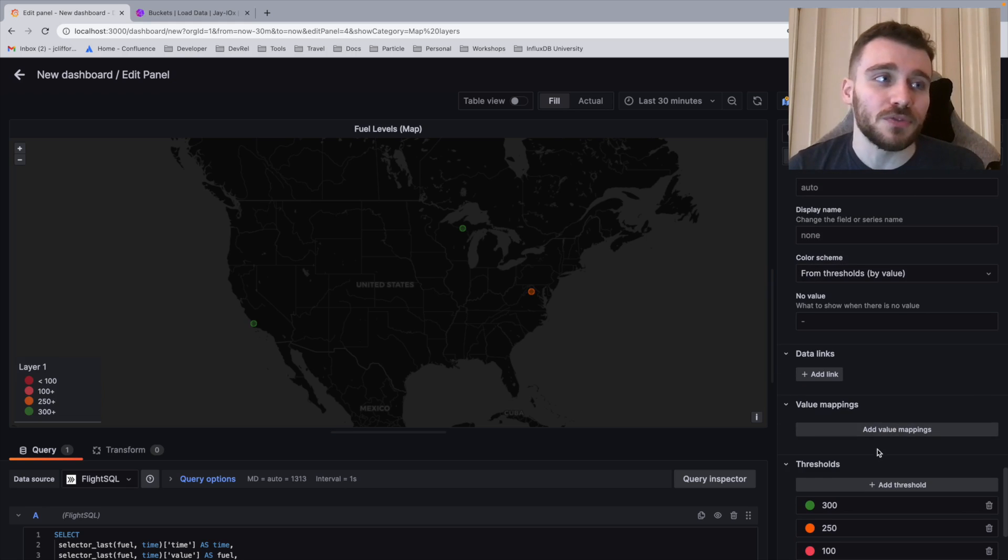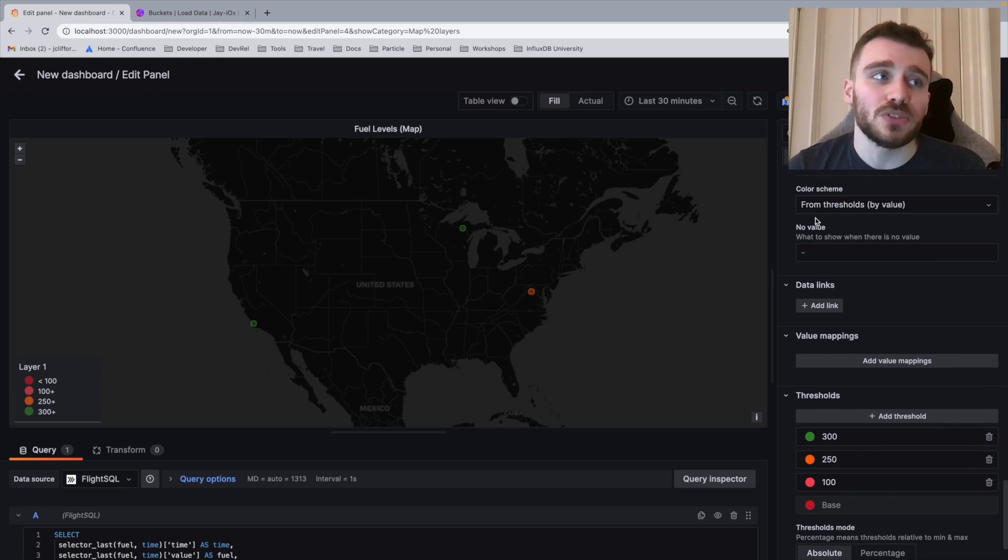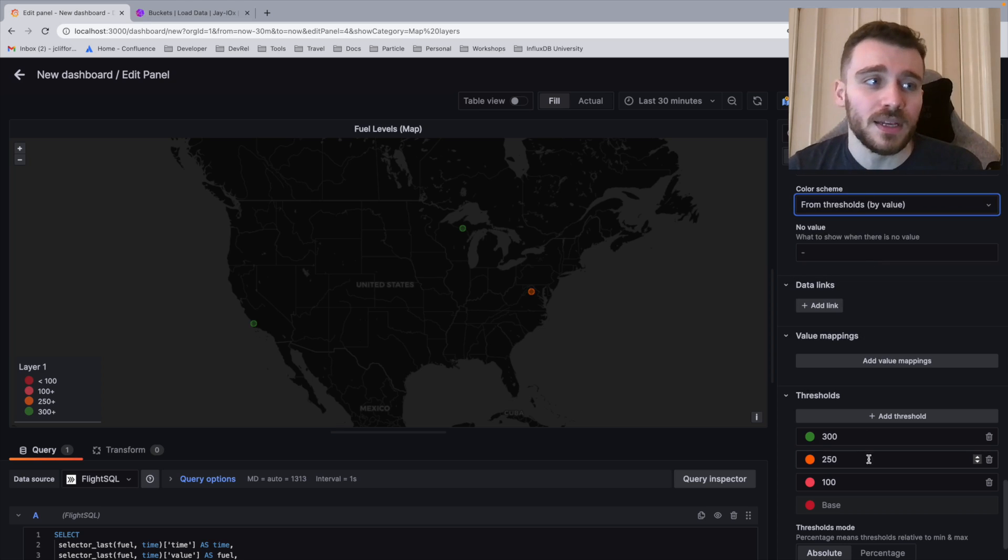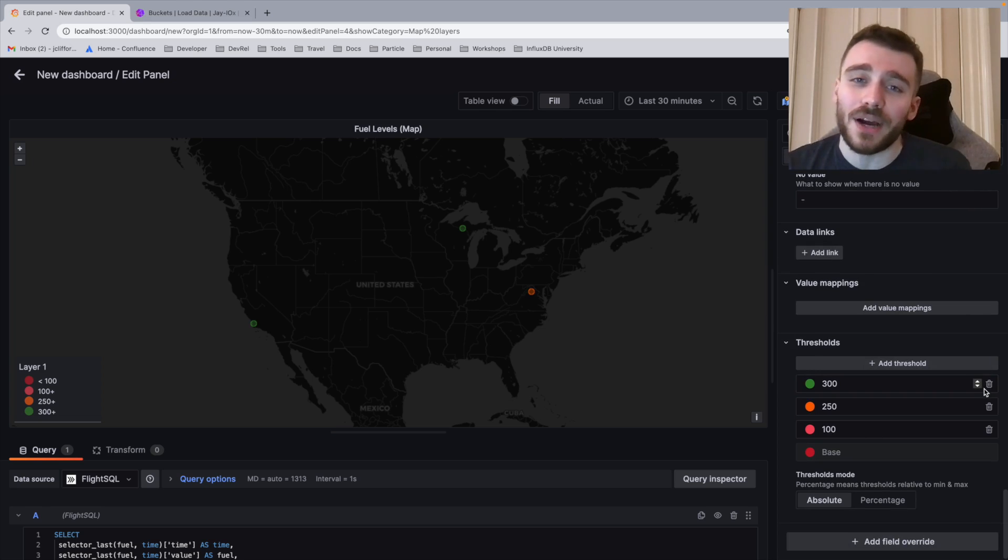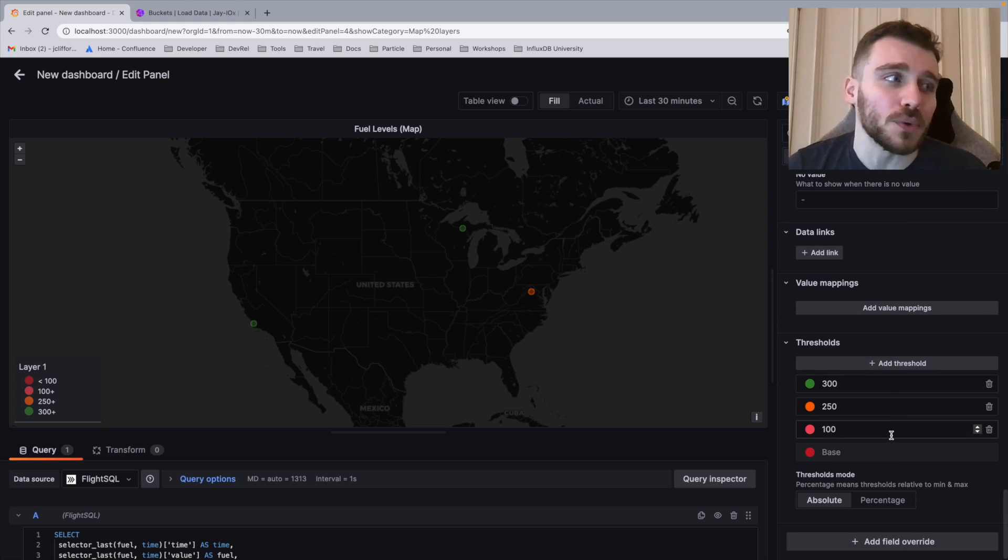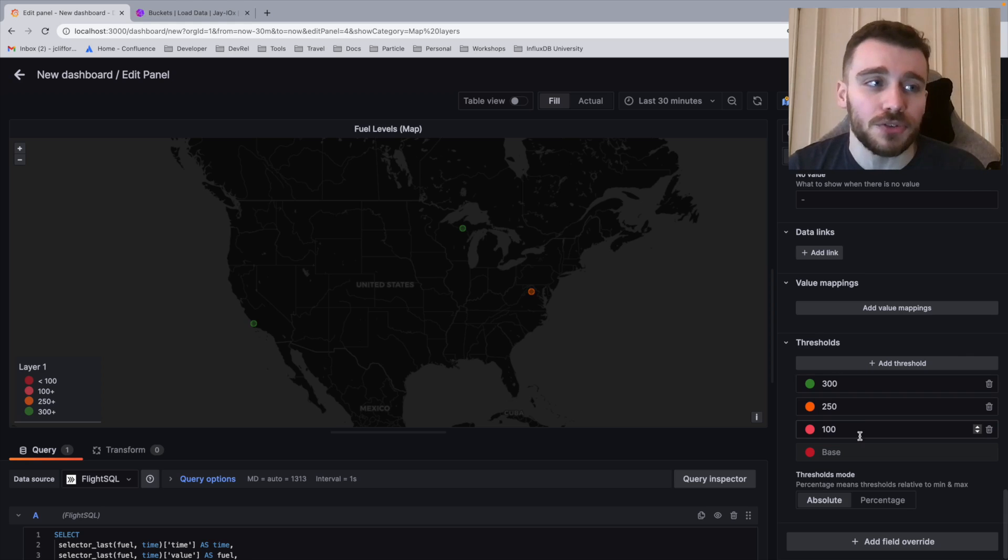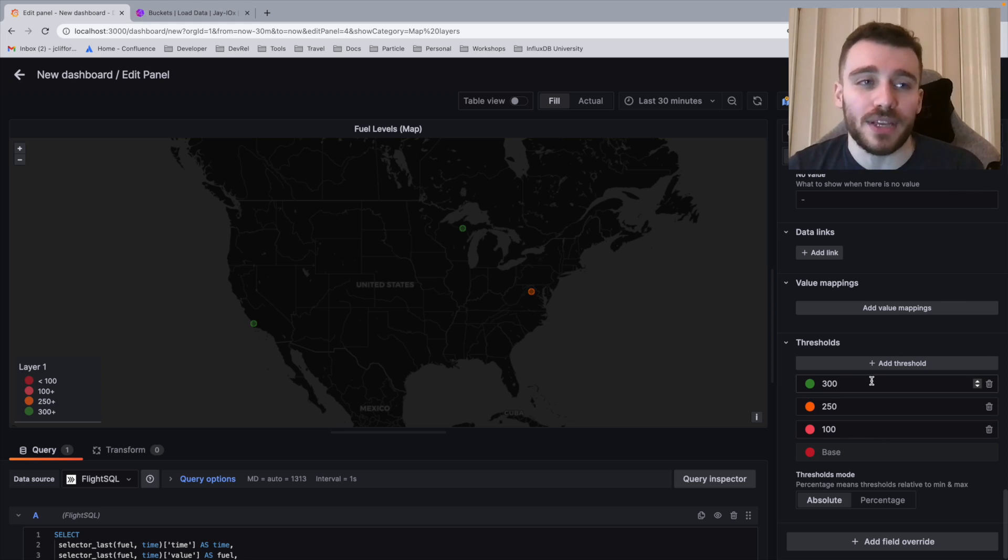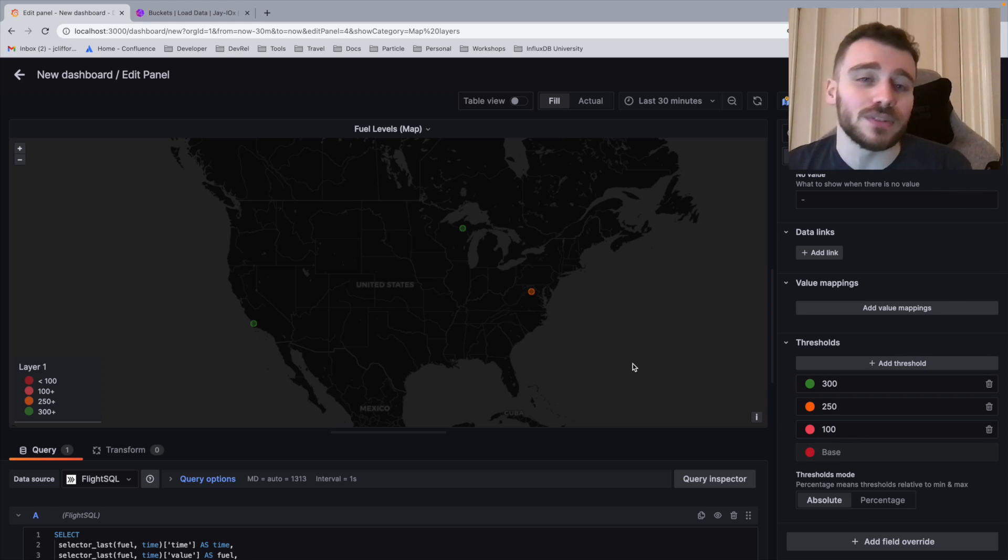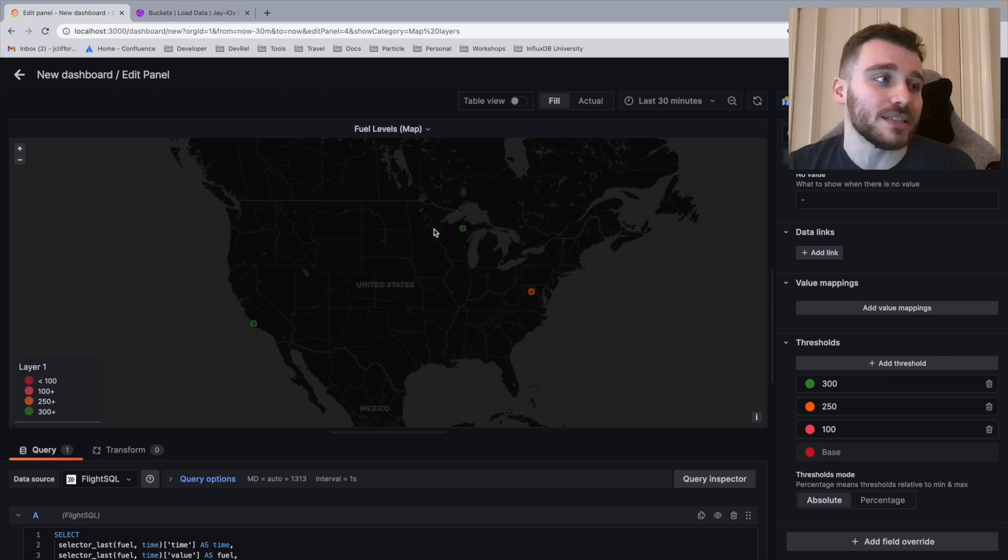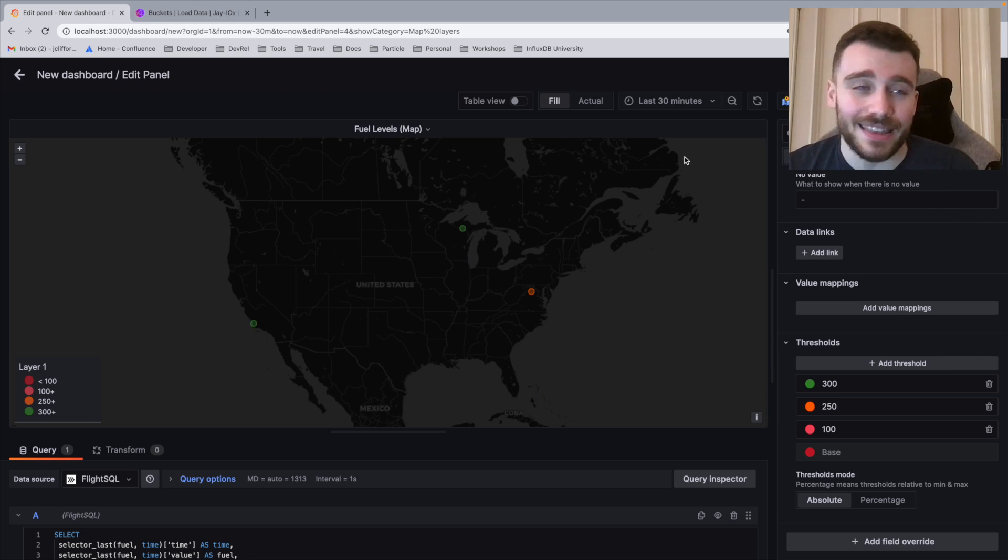Make sure that the color scheme is clicked on by threshold, by value, and then we're going to define our thresholds. Now I know within the generator data that the top level of fuel is 500, and obviously the bottom level of fuel is zero. So in this case, we've created thresholds for 300, 250, and 100. And now that you can see on the map, I have amber green depicting, depending on the fuel levels and their values.